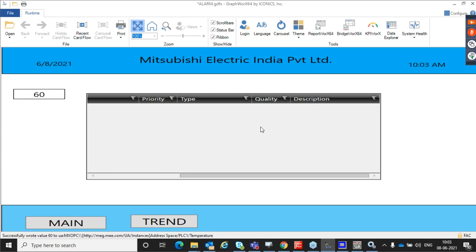So sometimes, without any operator confirmation, if the alarm is gone, it will be removed from the list automatically, or if any issue happens. Here in ISA mode, operator intervention is given. Whenever the alarm occurred, first he acknowledges it. Whenever the value changes due to some malfunctioning or some other data issue, the alarm is gone from the list. So the operator doesn't know how it is gone, what is this issue. That's the point of view only.